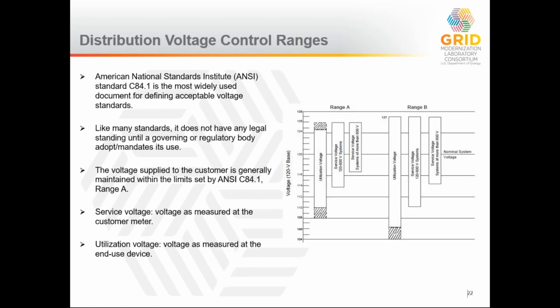One of the basic functions that is examined is voltage control. Voltage control is probably the single most important operational aspect, after making sure the system isn't overloaded, that utilities have to worry about. In North America, the most commonly used standard is ANSI C84.1. Most public utility regulators will select this as the standard, and what it does is basically say here's the range that voltage should remain within, and it's typically 120 volts, up to 126 and down to 114, so plus or minus 5%. This standard on its own does not have any legal standing until a regulatory body sets it as the standard. And this is the voltage as measured at the customer meter.